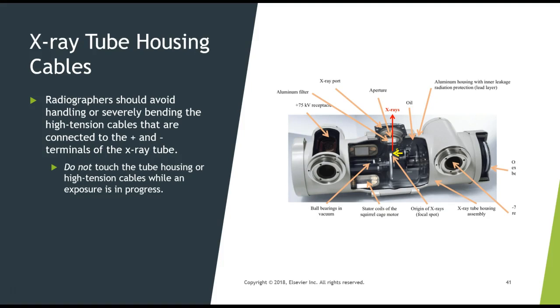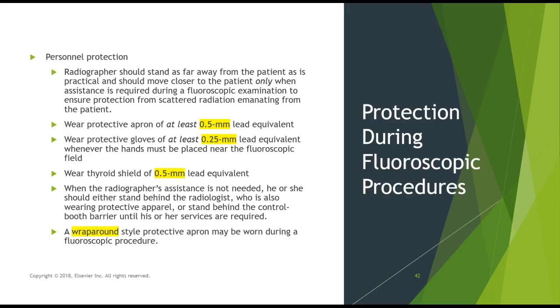You do not want to severely bend those high tension cables, and you never want to touch the tube housing or cables while an exposure is in progress. It should be impossible to do that if you are pressing the exposure button, but if you are in the room and someone thinks you're safe and you're touching one of these cables, the possibility of an electrical shock, let alone the leakage radiation that's close to you, is a concern.